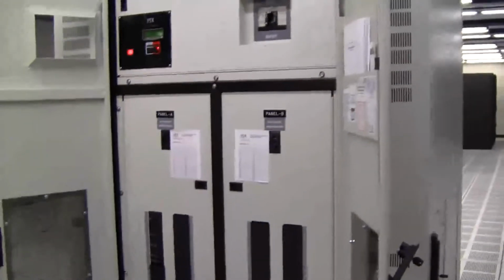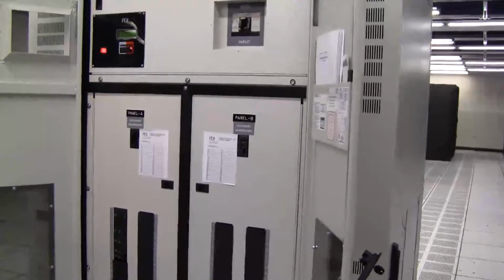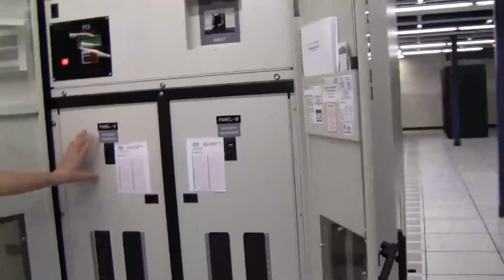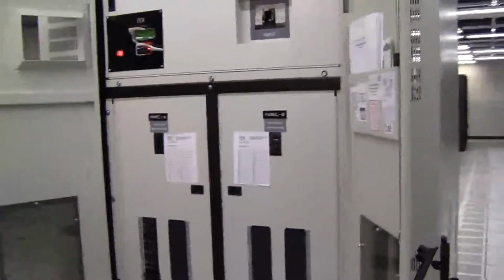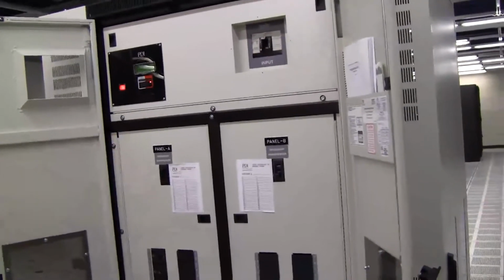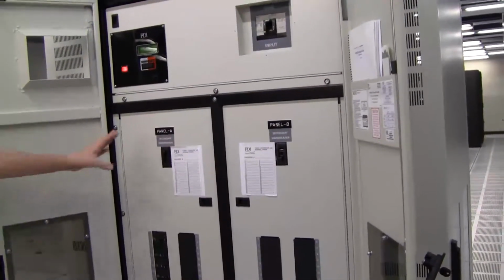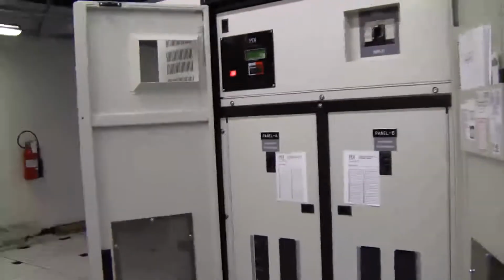What we do is provide an A and a B circuit inside the cabinets, so there are two power strips inside, panel A and panel B. This one actually has four panels on it - circuit A comes from here, circuit B comes from over there. That way you have dual redundancy. If you have dual power supplies on your server, if the power goes out on one, the other one picks it up.